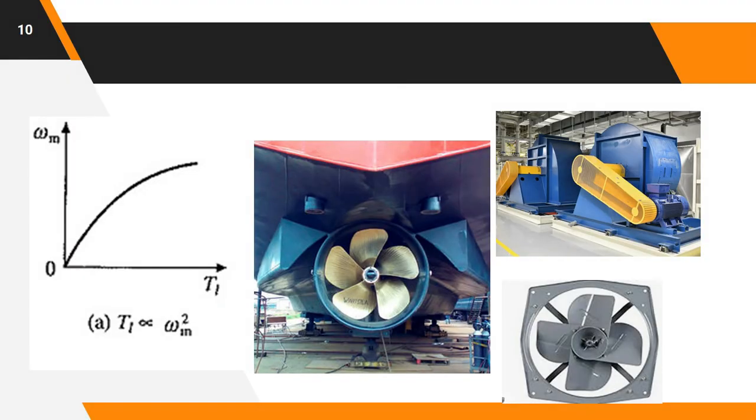First we will see the case where load torque TL is proportional to omega m square, that is, the torque is proportional to the speed square. That is nothing but windage torque being present. Examples are a blower, a fan, pumps, aeroplanes, ship propellers. Fan, compressor, aeroplanes, pumps, ship propellers, high speed hoists and traction are examples where the load torque is a function of speed square. In fan and aeroplanes the windage dominates.